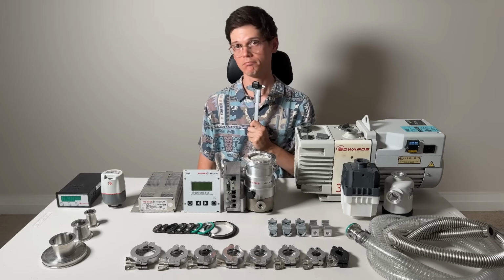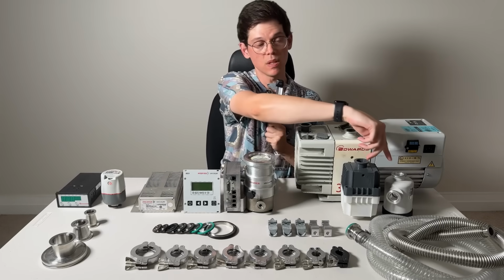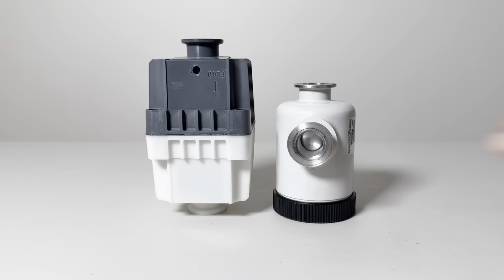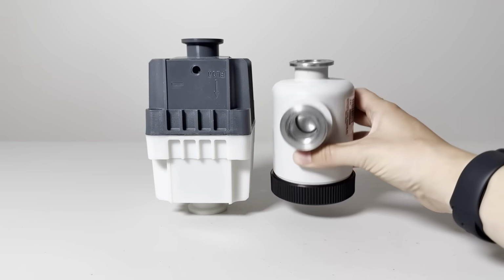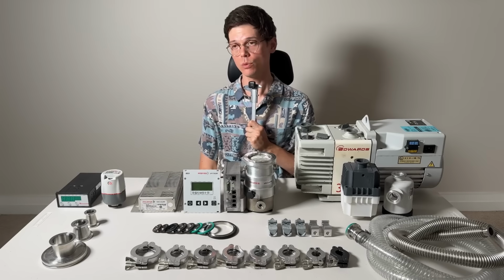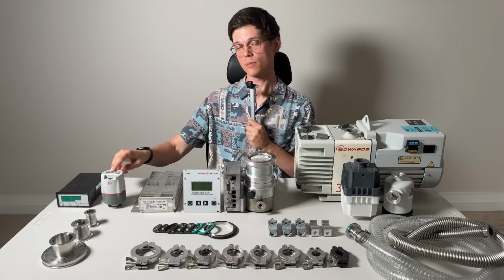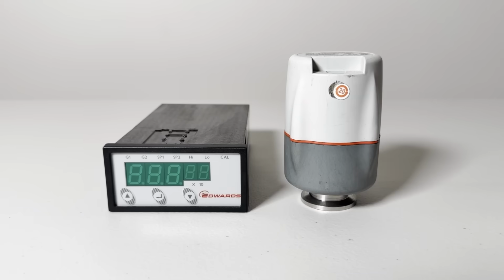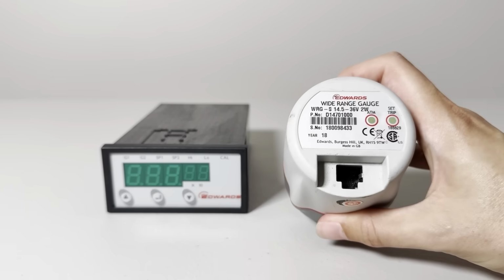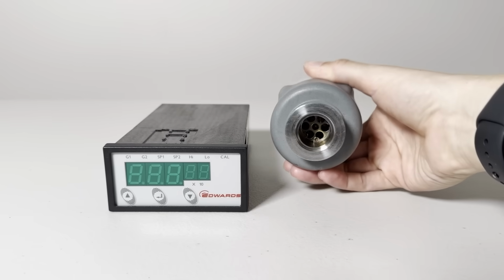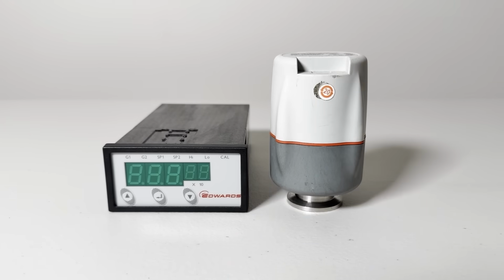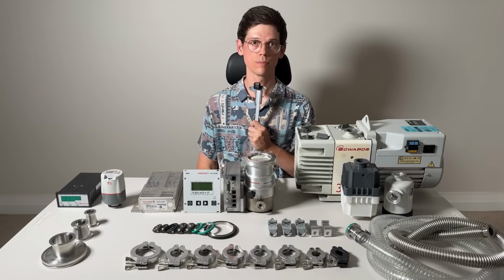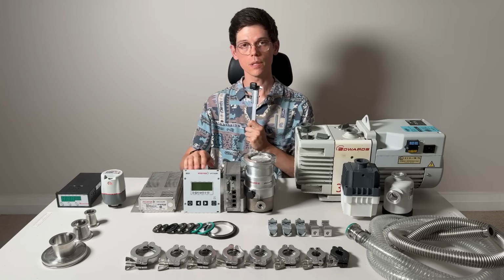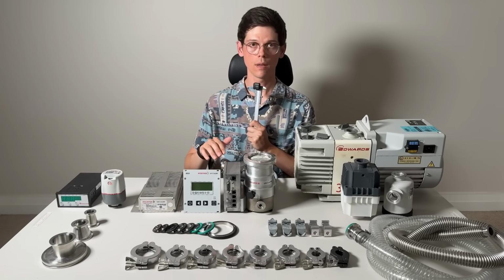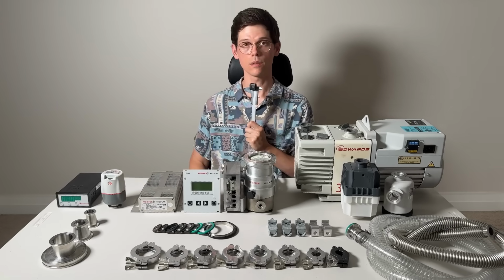So those are the pumps, but what else did I buy? These 2 parts at the front here connect to the rotary vane pump and capture any oil vapor that tries to escape. That's good because I don't want to be coating my walls with the stuff. This is the pressure gauge and its controller. It's a wide range gauge, which means it contains 2 mechanisms for measuring pressure, and it automatically swaps between them, so it'll work over the whole range of pressures that we're dealing with. Finally, we've got some controllers and power supplies to run all of the equipment, plus the bits and pieces we need to connect it all together.